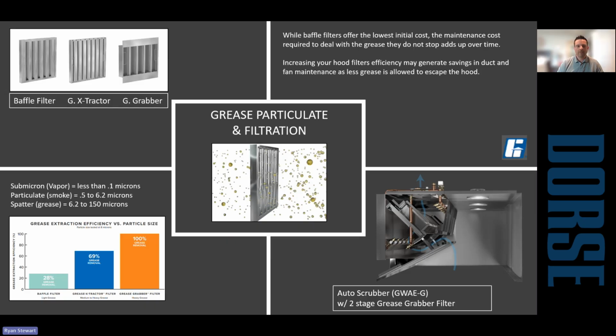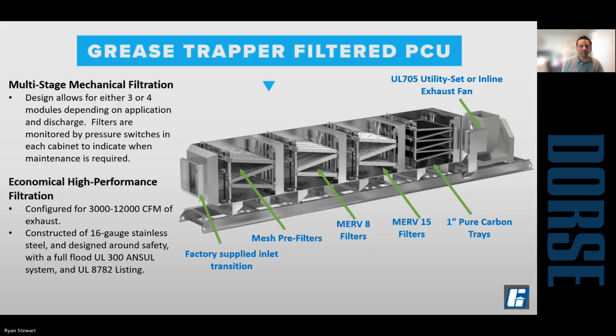There is an upgrade. The grease grabber filter, it's a 2-stage filter. And so the second stage is a porous ceramic bead. It does require a lot more maintenance. So they offer a scrubber hood where there's actually a wash system in the hood to clean that ceramic bed. So this is going to be one type. It's mechanical filtration. We're going to look at the cooking equipment lineup.